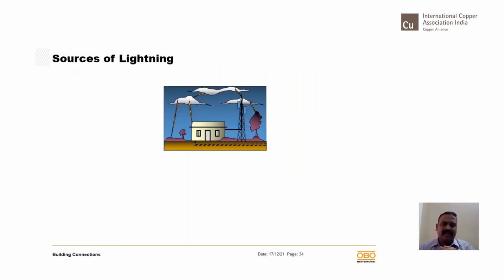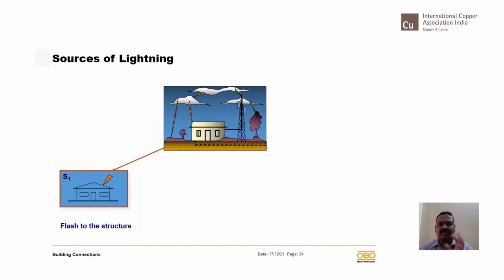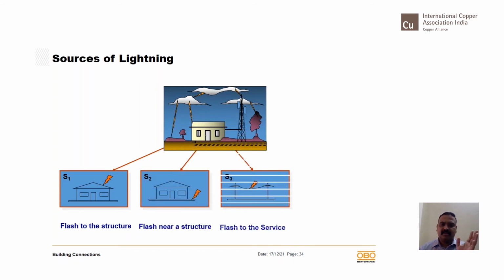Now, sources of lightning. As we discussed in the previous case study which I explained, one was a strike on the building, and the other was on the service cable entering. So the standard defines four sources of lightning strike. Source 1, lightning striking on a structure: the damage caused because of lightning hitting a structure. Second, lightning striking near a structure. The third is lightning striking on a service entering a structure. These can be your power, voice, data, communication. Any of these lines can be considered a service to the structure.